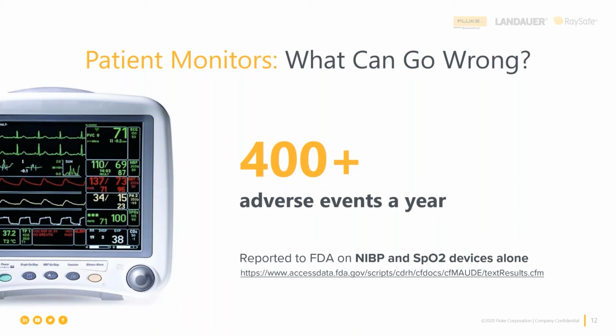Hey, Mike, I'd like to tag in there. Something we might not have mentioned before is that we were talking specifically about the ICU, but a lot of these monitoring systems will go out to a central monitoring station, be it housed at your hospital, at another hospital, or at a third-party location. So are those parameters set up right? It might not be that the monitor isn't doing its job, but did we set up the parameters to trip at the right levels and the right alarms and the right conditions to alert us when these situations have happened? One of the things I get to work on with our customers is using some of the devices to simulate some of these alarm states to trigger that central monitoring station and then make sure the appropriate responses have been happening. No, that's a good point.